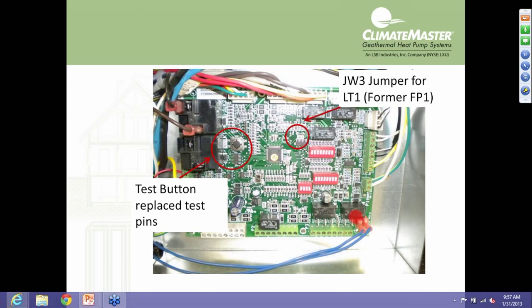It's now called LT1. And if we're doing a closed loop and we've got antifreeze in the loop and we need to have a minimum of 15 degrees freeze protection, then we can cut the jumper. And again, if you're doing a closed loop and your entering water temperature is going to drop below about 45 degrees, you're going to need to put antifreeze in that loop and cut that jumper. Otherwise, you're going to have nuisance trip outs on LT1. So that's the jumper that does get cut. I always recommend you have the power off to the board when you cut that jumper, so that there's no chance you're going to short something else out on the board in that process.